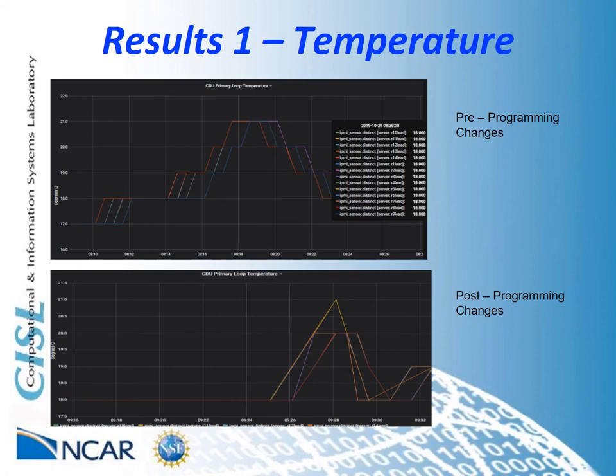I wanted to go over some of the hard data we have to show what we feel is a successful change in programming and sequence. These graphs show the supply temperature provided to the CDUs from the NWC chilled water system. The top graph shows the temperature reaction before the changes were done and the modes were run in a serial manner. The system rises from 18 to 21 degrees Celsius and then back down to 18 degrees Celsius over a span of roughly 10 minutes, and the system takes some time to recalibrate.